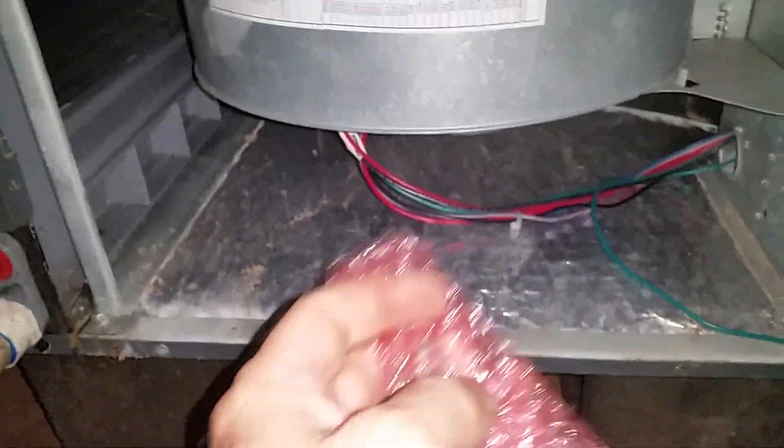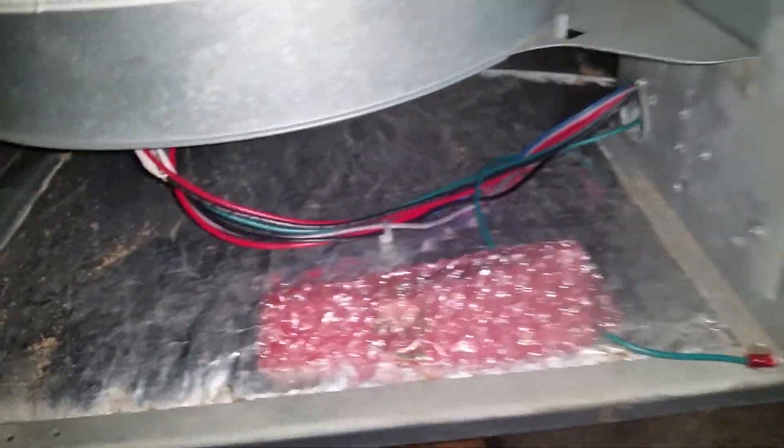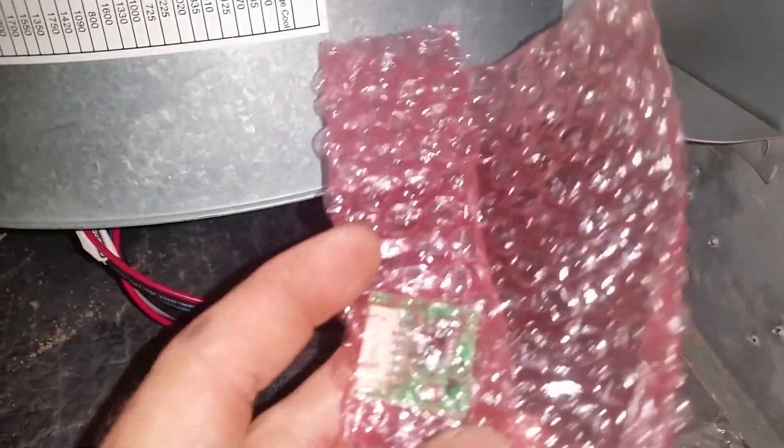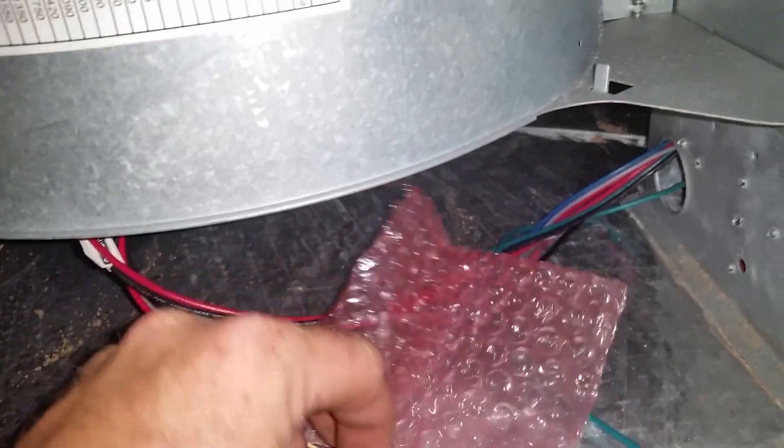Today we have a situation with a heat pump where we had to replace the variable speed drive and the module because both of them are shorted. In this particular case, there's something you have to do. Goodman units don't come with the programming — the programming is usually done at the factory and maintained in the board. If the board has not been replaced, the original board will store it as well. But if you have to replace both the variable speed drive and the circuit board, you must order the memory chip at the same time.